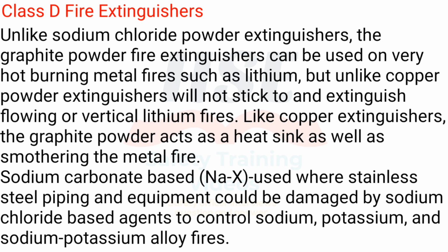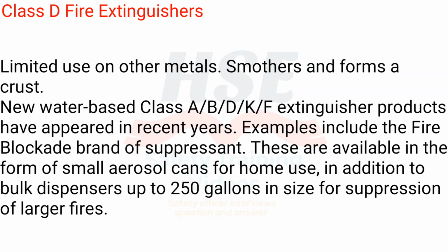Sodium carbonate-based, NaX: used where stainless steel piping and equipment could be damaged by sodium chloride-based agents, to control sodium, potassium, and sodium-potassium alloy fires. Limited use on other metals. Smothers and forms a crust.